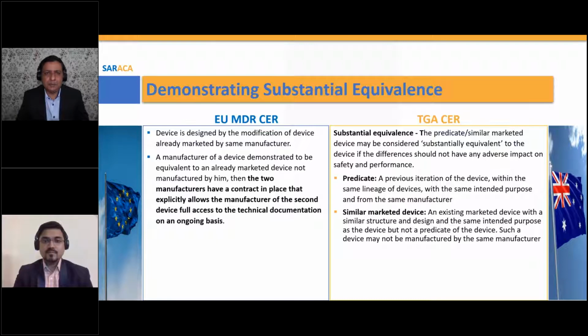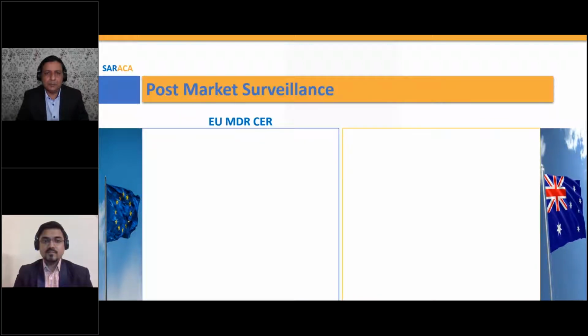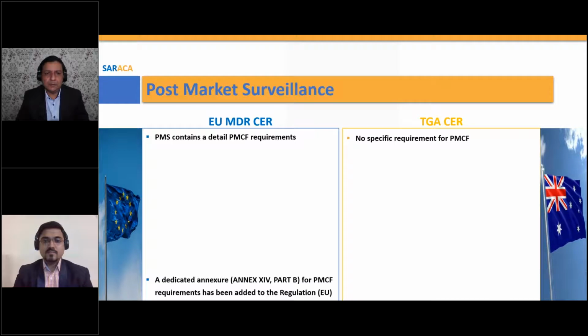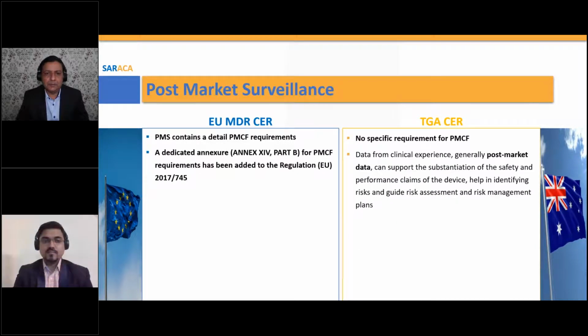The next slide, we will be talking about post-market surveillance and the differences between the two. The TGA has no specific requirements for the PMCF, unlike the EU.